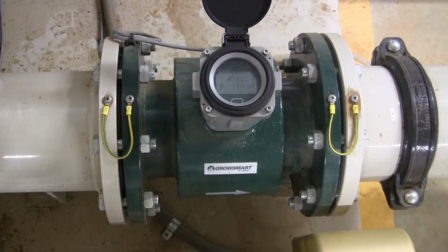So what you're looking at here is a magnetic flow meter. It's accurate to within almost 1/10 of a gallon. Many of you are used to the Data Industrial 220B, which is a brass mechanical meter that is only accurate down to about 100 gallons a minute. This is just newer technology, and with some of the recording information that's required by a lot of states now, a lot of people are going this direction.